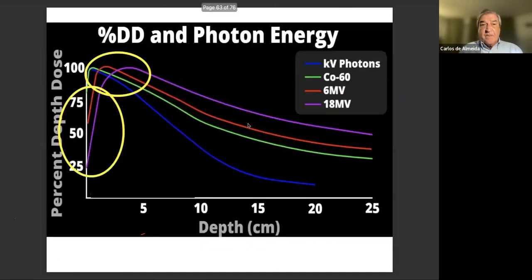Next slide. You can see, for instance, this is the 4 kVp photons. Here you see the maximum dose at the surface. But as you go to cobalt, the point of maximum is about 5 millimeters. Then you go to 6 MV, which is about 1.2 centimeters, and 18 MV, which is about 3 to 4 centimeters. The shape of the curve is about the same, but this region is very important to know because of the clinical application. And why do we use 5 centimeters? Because we are just about here, away from these large gradients that surround the point of Dmax. The next slide.